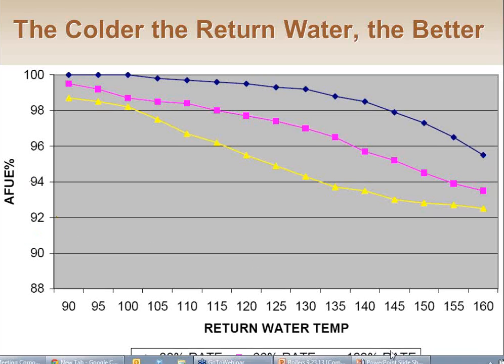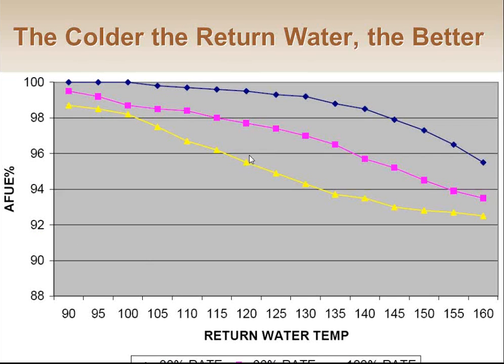This example here is a very similar chart. This is for a very specific boiler that we use in our training classes in our lab that we live fire. So it works very similarly. At 160-degree return water here, this is a 93% efficient boiler, right? If I look at it that way, it's 93% efficient. Boom, right? And if I start dropping my return water temperature, as you can see, around 130, it spikes up. It's not quite as dramatic a spike as the other one, because this is already a high efficiency boiler, so there's only so much room to go here. But you can see it does get more efficient as I get colder.